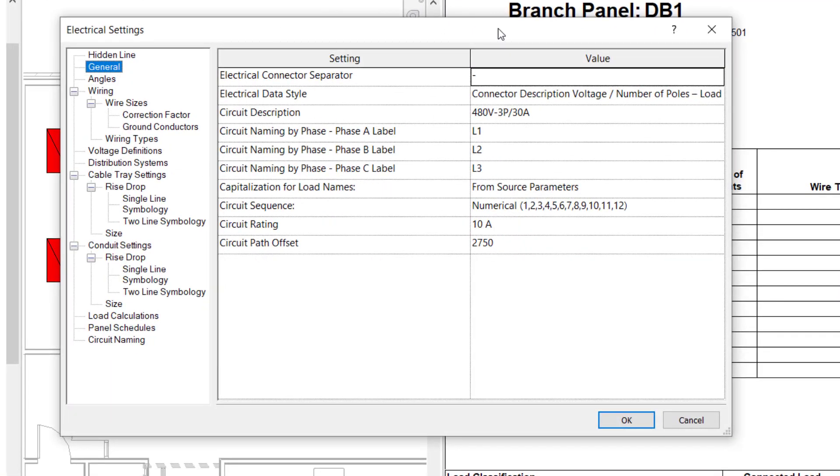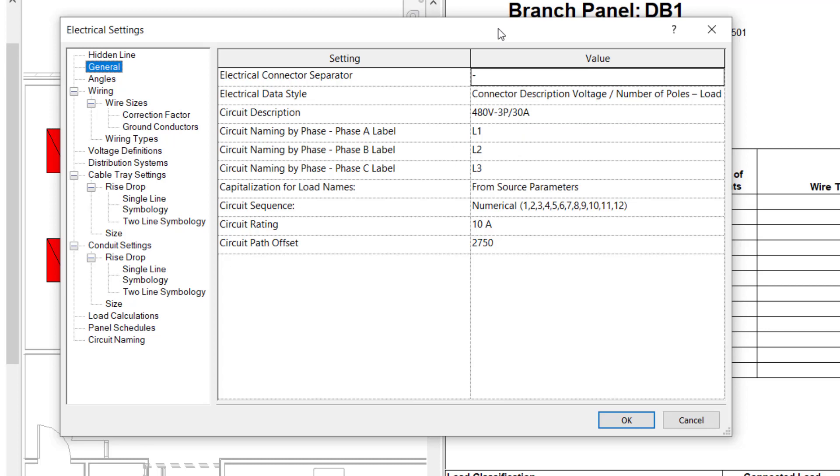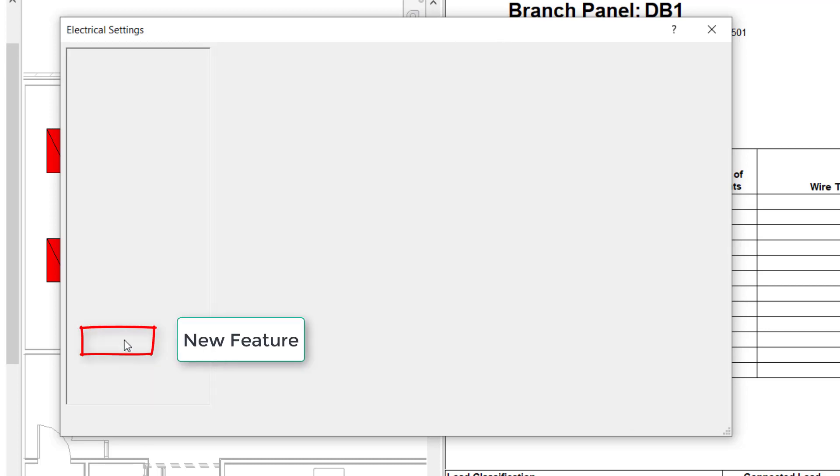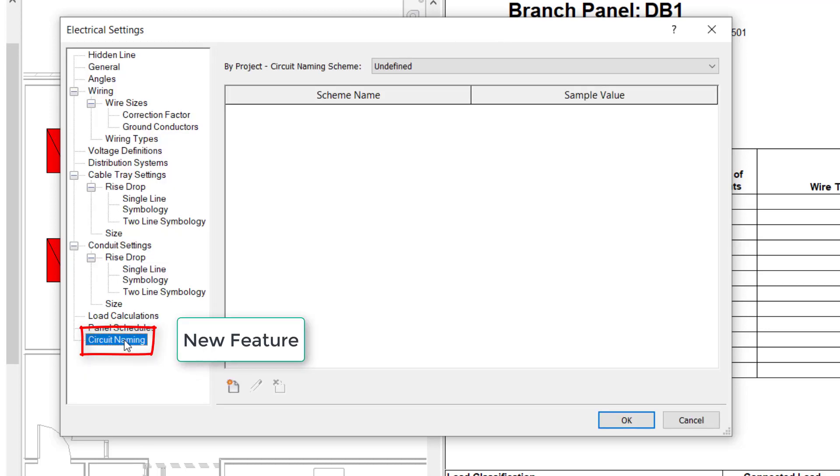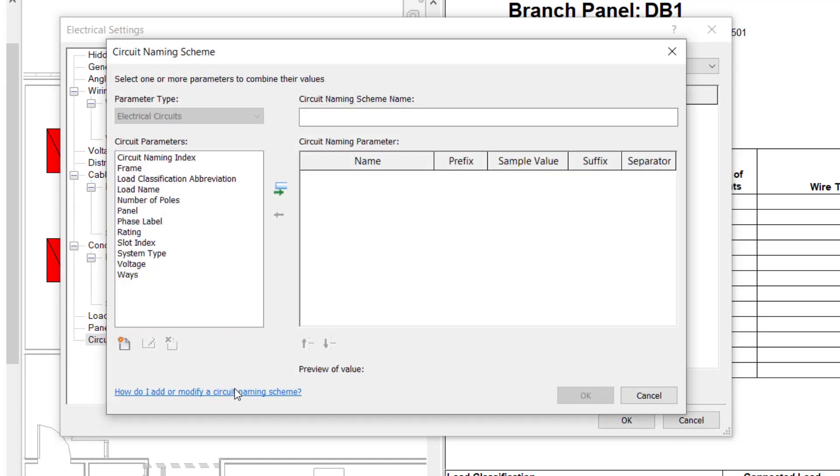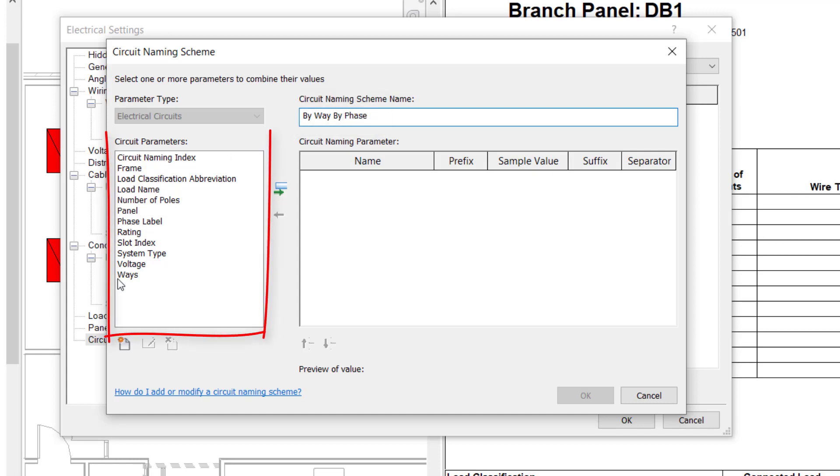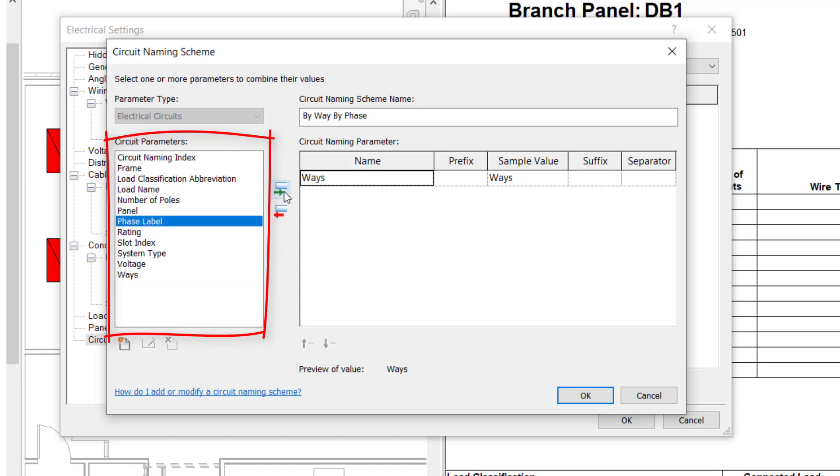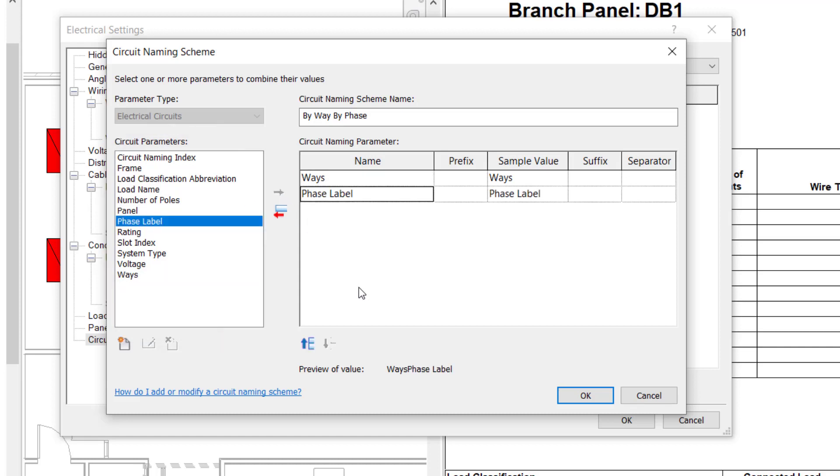It starts in the electrical settings with a review of the phase naming. Once this is set to UK standard we can now look at the addition of circuit naming types. This feature allows a user to create a new circuit naming scheme. Here I will name the new scheme by way and by phase. After naming the new scheme simply add the fields of data you want to appear in the circuit reference much the same as adding fields to a schedule. A prefix, suffix or separator can also be added if required.